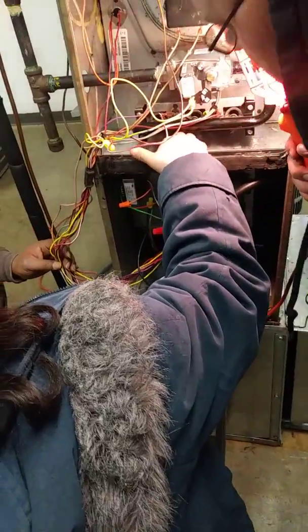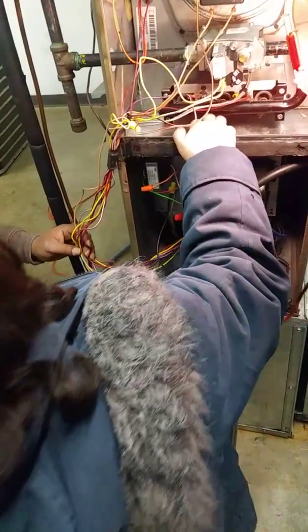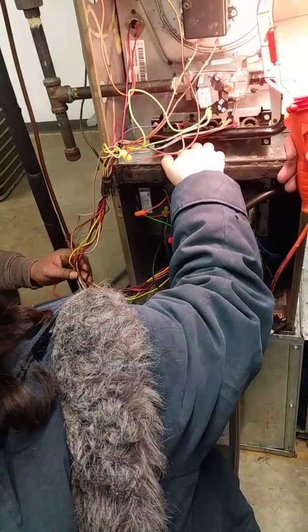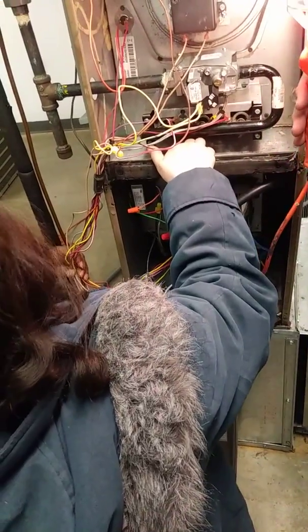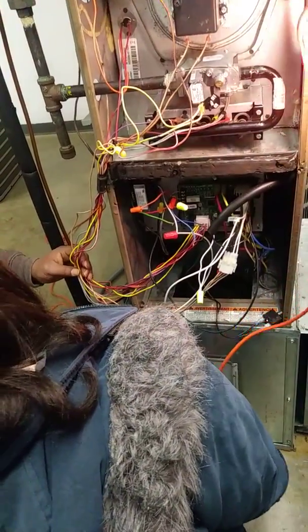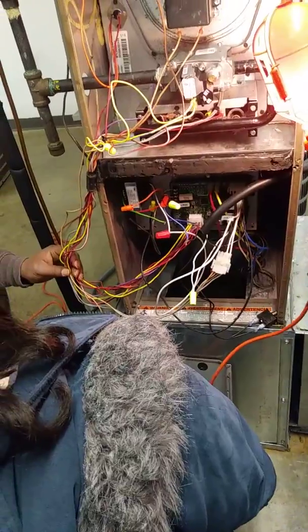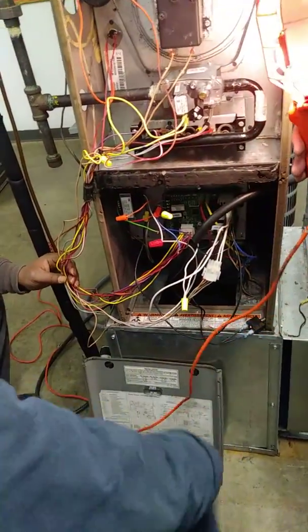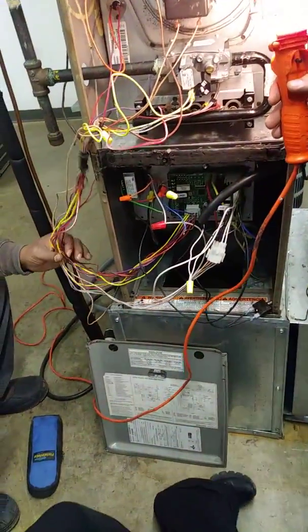So we had to work on this furnace and we took the door off. Normally the door, the power will go off when you take the door off. But in this case it won't, because there's no wires going to the door switch, to the switch to cut it off, so you got to make sure you cut it off at the switch right there.